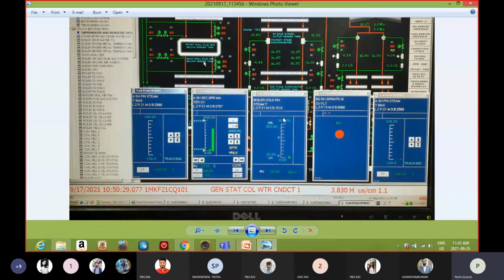So one can see 27.2 is a boiler cold RH steam temperature. I am just giving the example because I have taken the screenshot of another parameter. So this is boiler cold reheat steam temperature. Currently it is 26.58. High alarm limit is 350. Low alarm limit is 20, and it has a range of 600. So this is analog input.